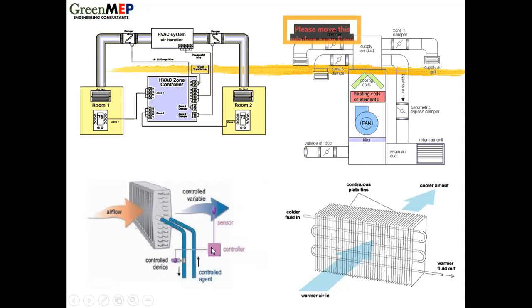The controller, the brain, communicates to the valve, the chilled water valve. There's a motor, communicates with the motor power supply, and then voltage is decreased or increased, and then the valve is open, allowing more water. When the valve is open, there's going to be a static pressure difference, a pressure change in the water supply circuit, the water circuit. And then when that happens, the chilled water pumps' speed goes up.